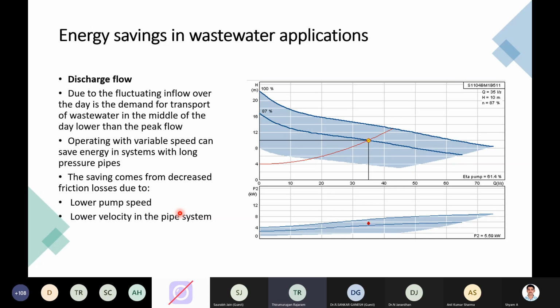So these two things, and over and above, you have an energy saving option in this case, because here the system is responding truly based upon your inflow demands. Whenever your demand is very low, or whenever your demand is very quick, the pump should respond very quickly to take the water out. That scenario we could see much in rainy times, where your inflow is very fast, so the pump has to respond very quickly, and in lean time it can respond very slowly. So, maintaining the required velocities in your pipeline.